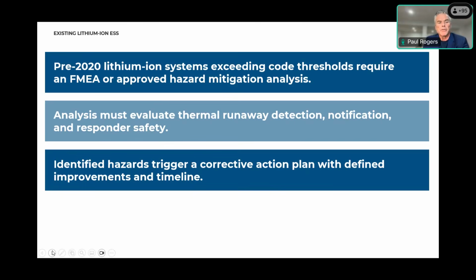The pre-2020 lithium-ion systems exceeding the threshold did require an FMEA and an approved hazard mitigation analysis, and that's still in place today. The analysis there must be to evaluate the thermal detection. That's usually done as part of your listing in UL 1973, which covers how thermal runaway is actually detected and how the BMS should interact with that to make sure we do not get thermal runaway from taking place. But we also want to make sure fire department and responder safety is incorporated into that.